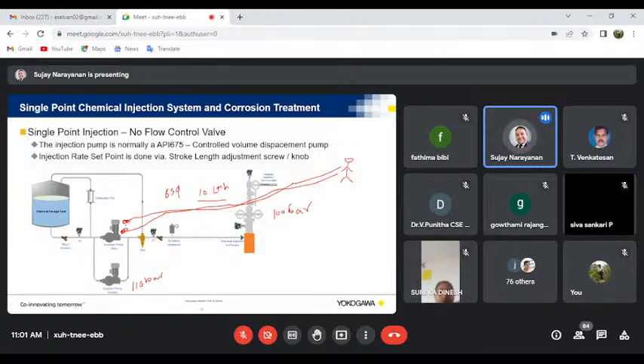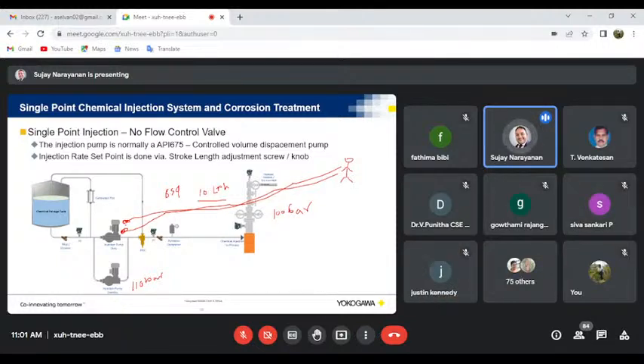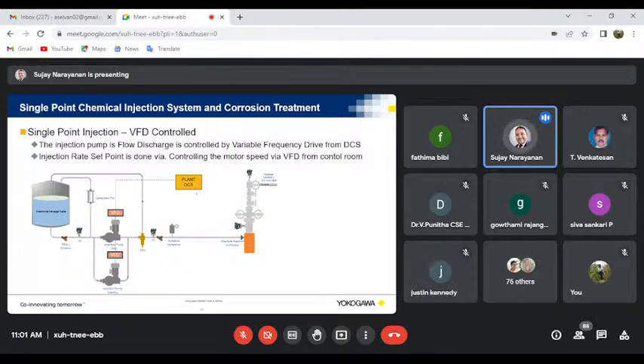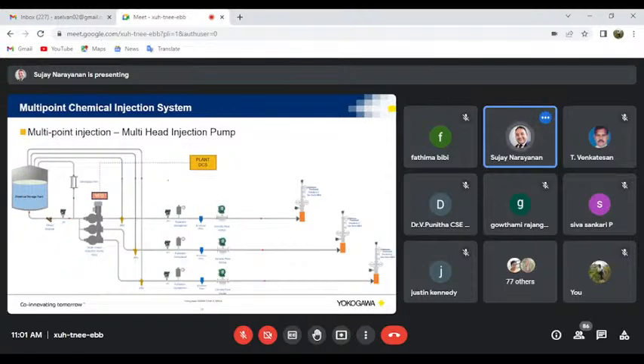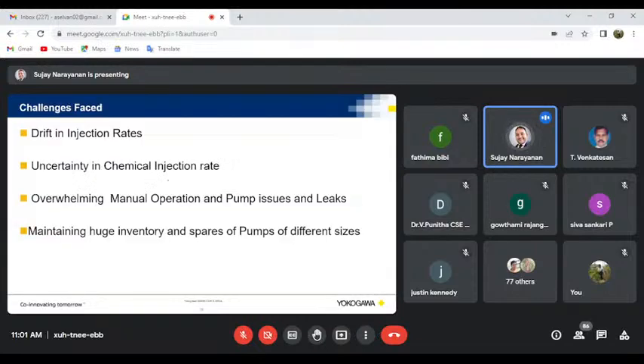I'll tell you the reason why the pump drifts. Even if it is a remote operation, it is still inefficient, because every time he needs to keep track of whether the pump is drifting or not. If you see the essence of it, everything is reactive over here. It's not proactive, like Industry 4.0. Everything is reactive; that's the main point I'm trying to drive. So, uncertainty in chemical injection rates and overwhelming manual operation is what they are mostly frustrated with.